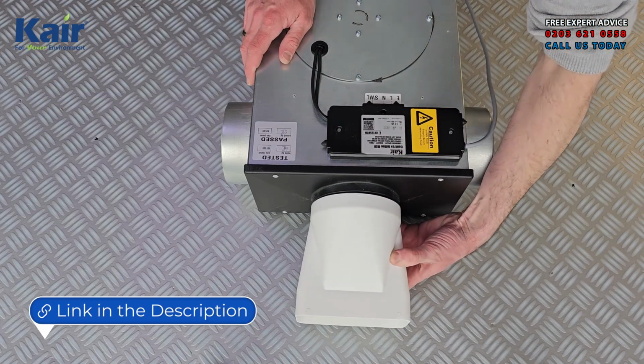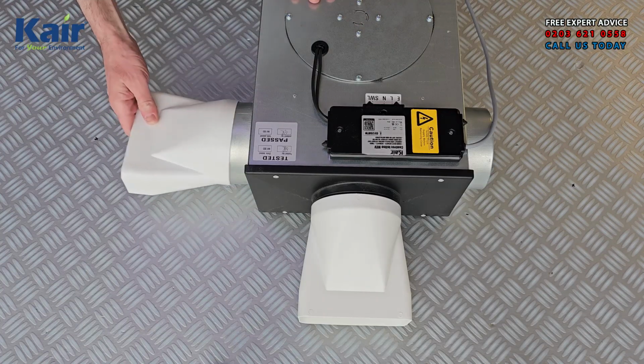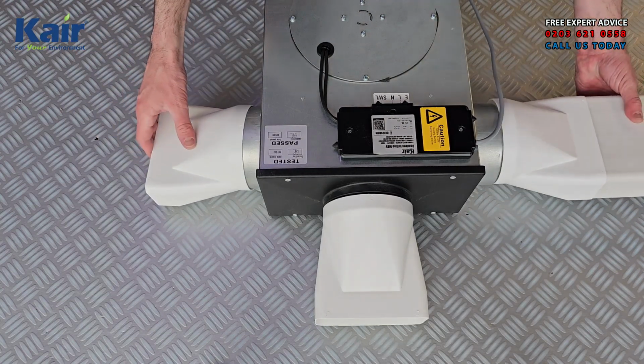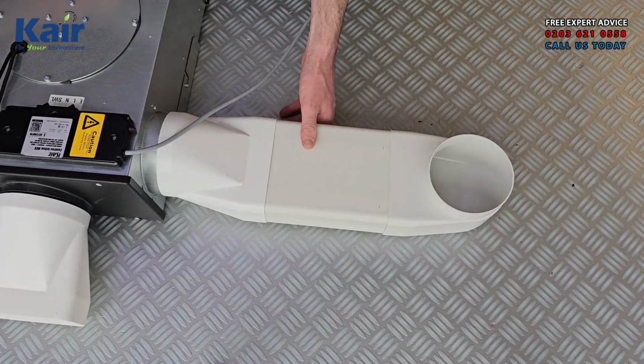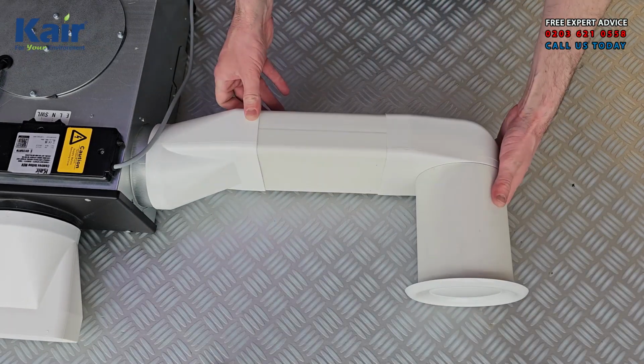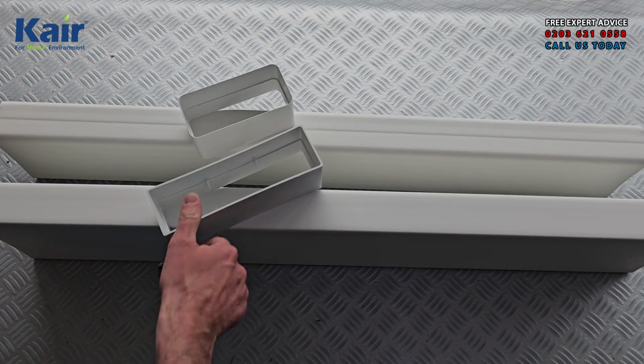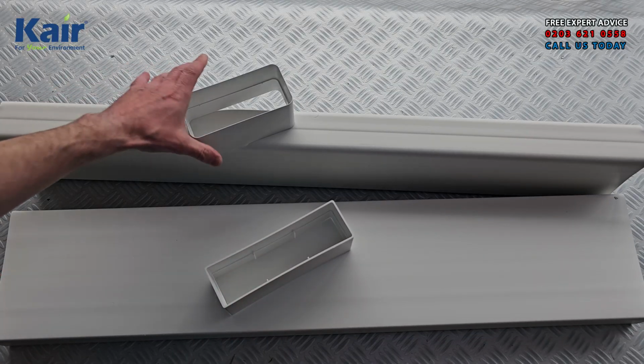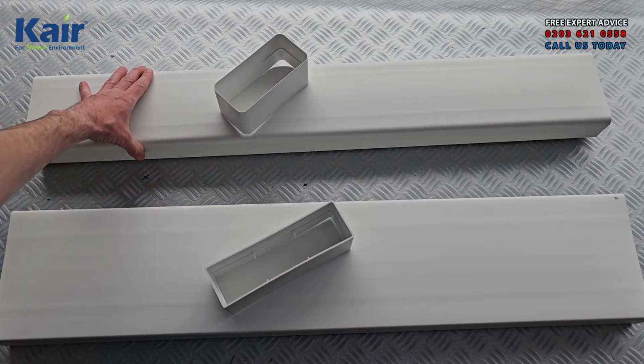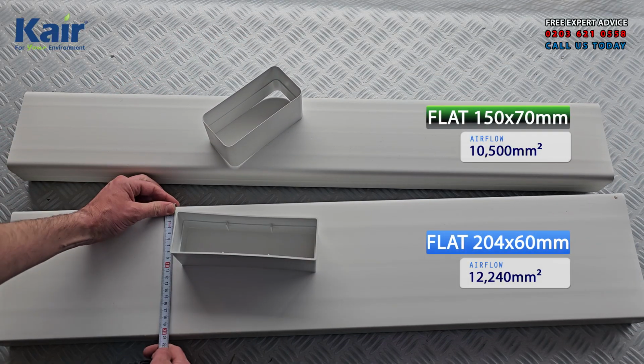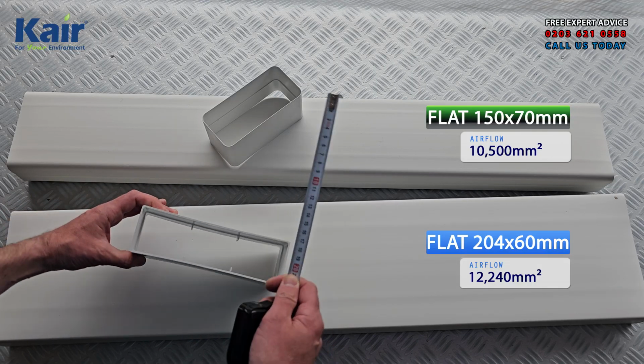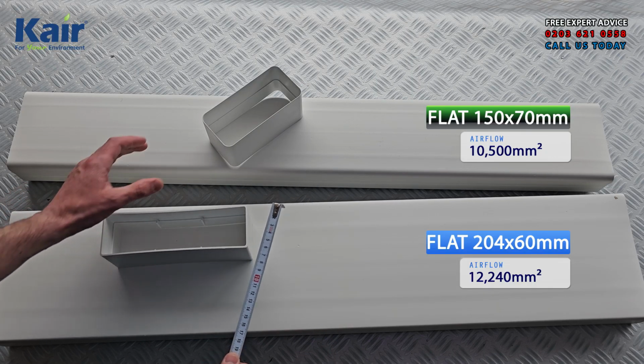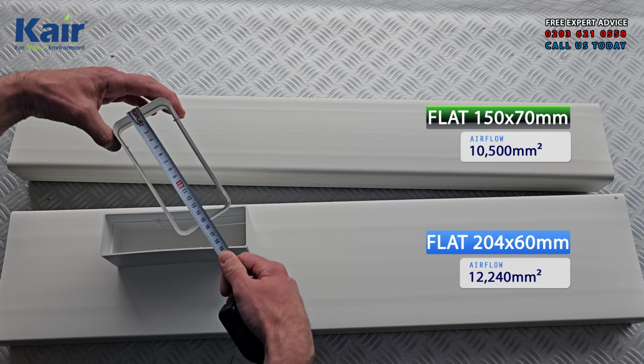However, the 150x70 system is a useful alternative, providing similar airflow while offering a different shape for installations where more depth is available but width is limited. Compared with the 204x60 system, the 150x70 duct is narrower but deeper. This can be useful in ceiling voids or boxed duct runs where space is restricted in one direction.